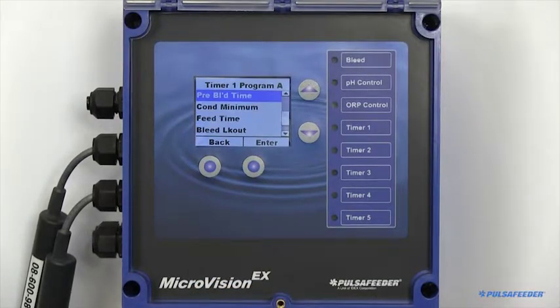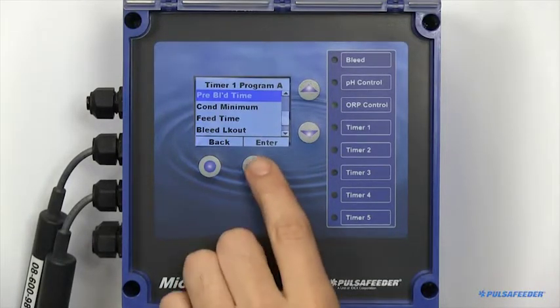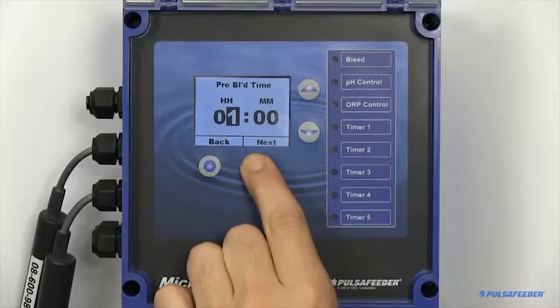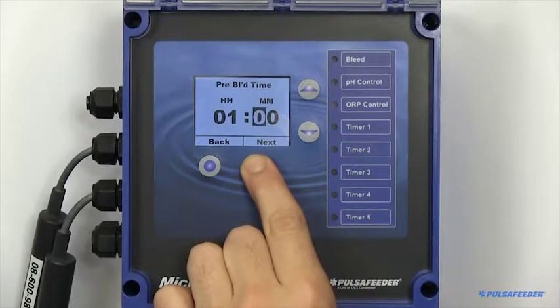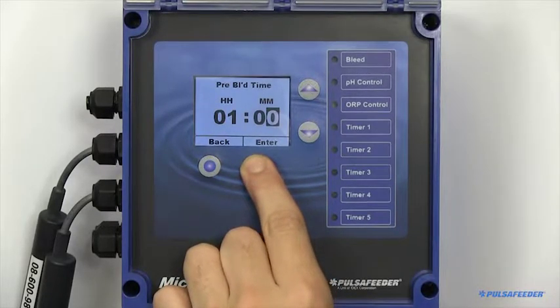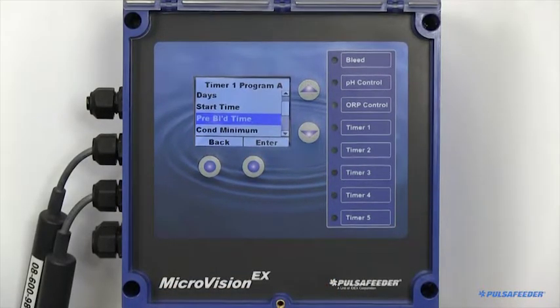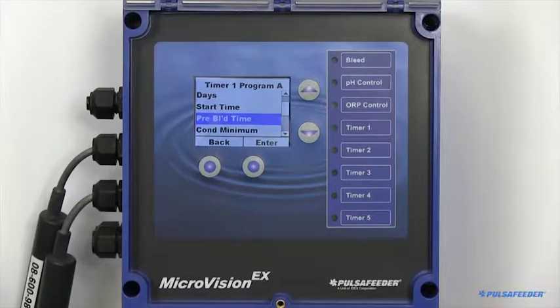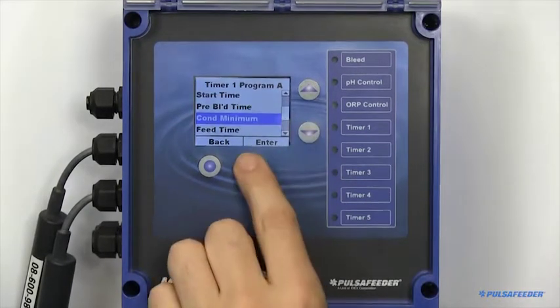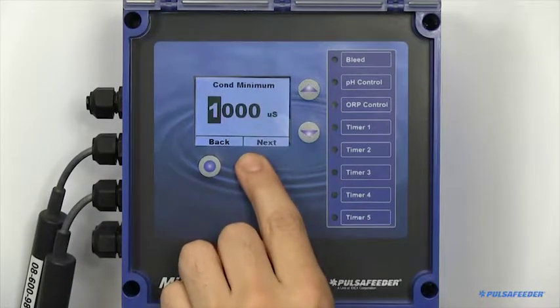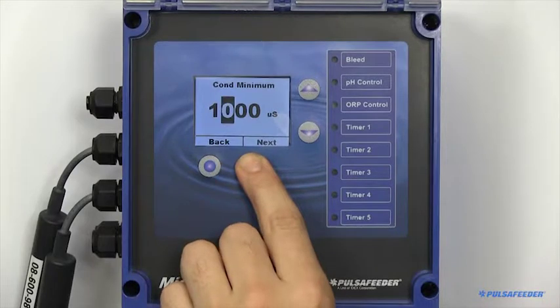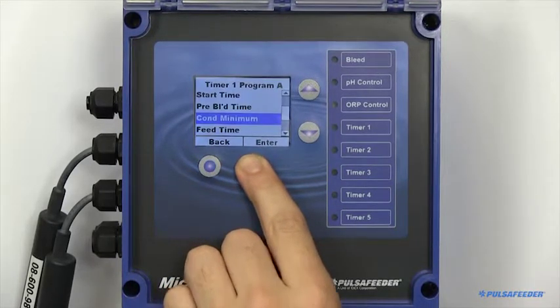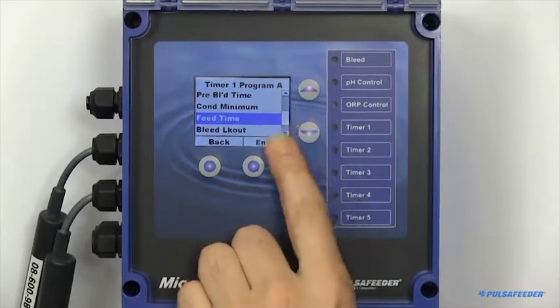A prebleed time is the maximum amount of time you would like the bleed function to be force enabled prior to a feed cycle. If there is a minimum conductivity you would like the tower to reach to immediately begin your feed cycle, this can also be set.